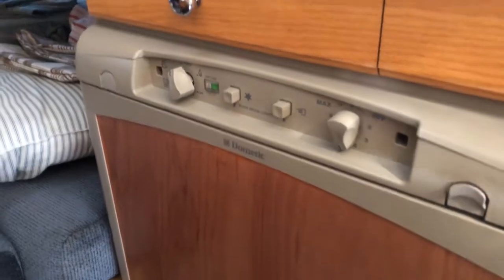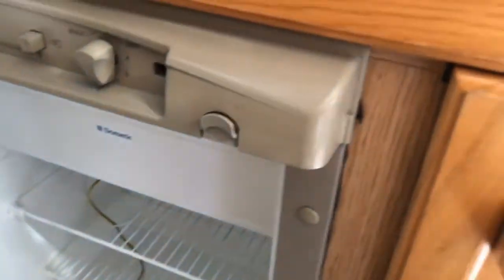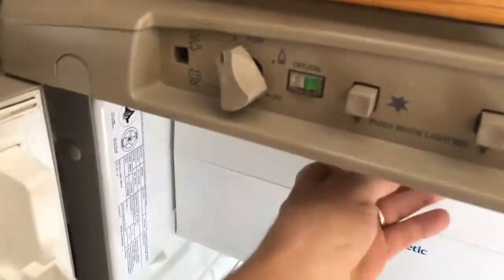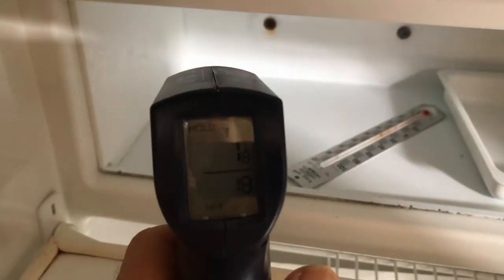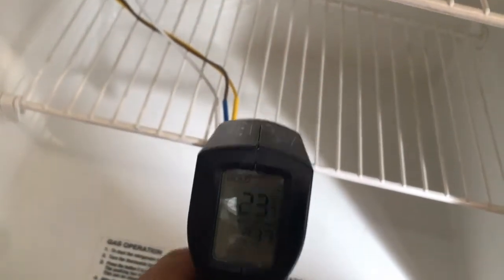It's been an hour. The ambient temperature outside is 28 degrees - nice warm day. Inside the freezer it's reading 1 degree - that can't be right after only an hour, but yes, about 1 to 1.8 degrees. The fins are still around 23 degrees.